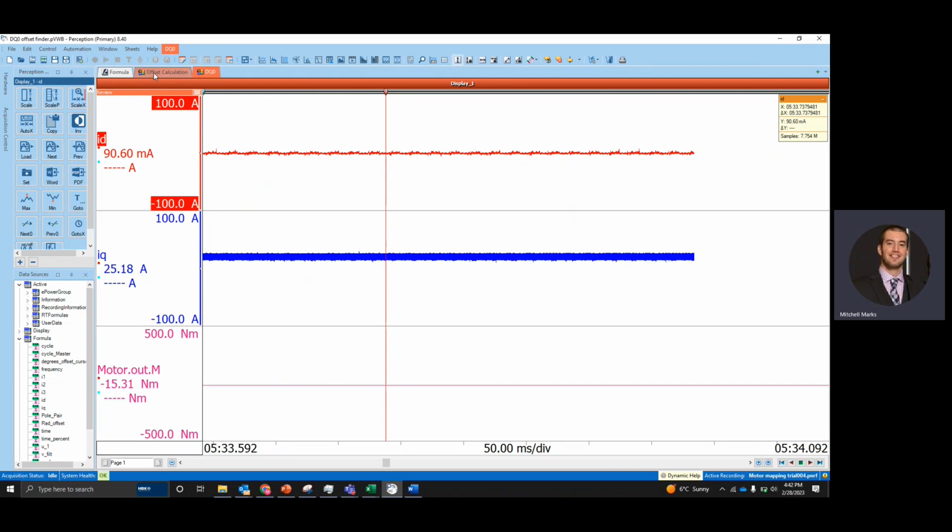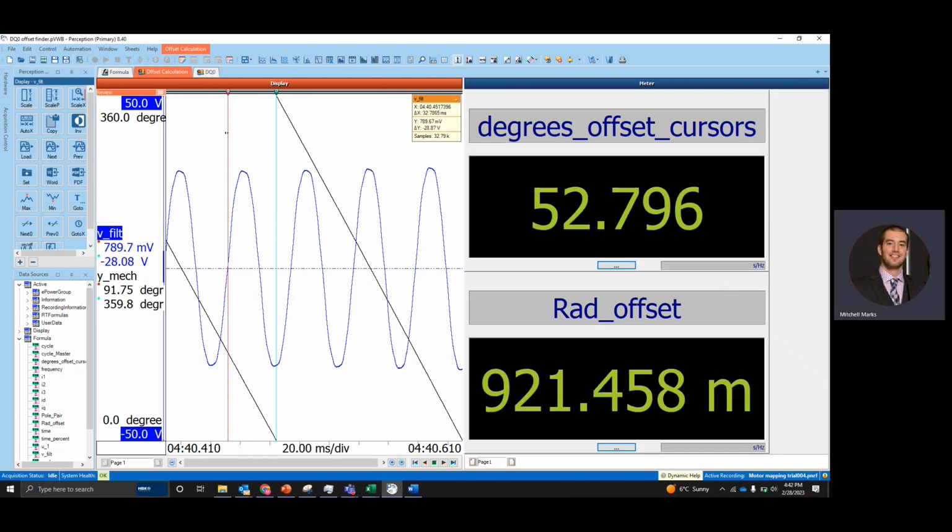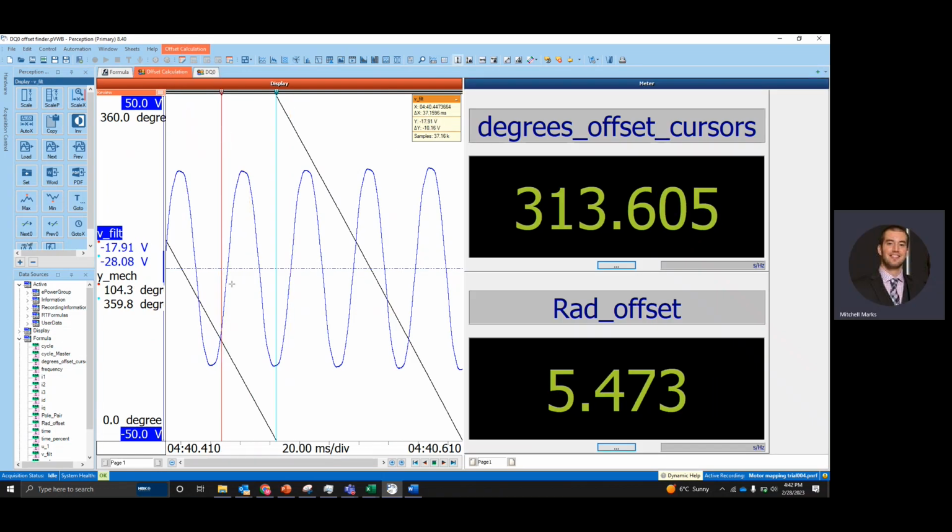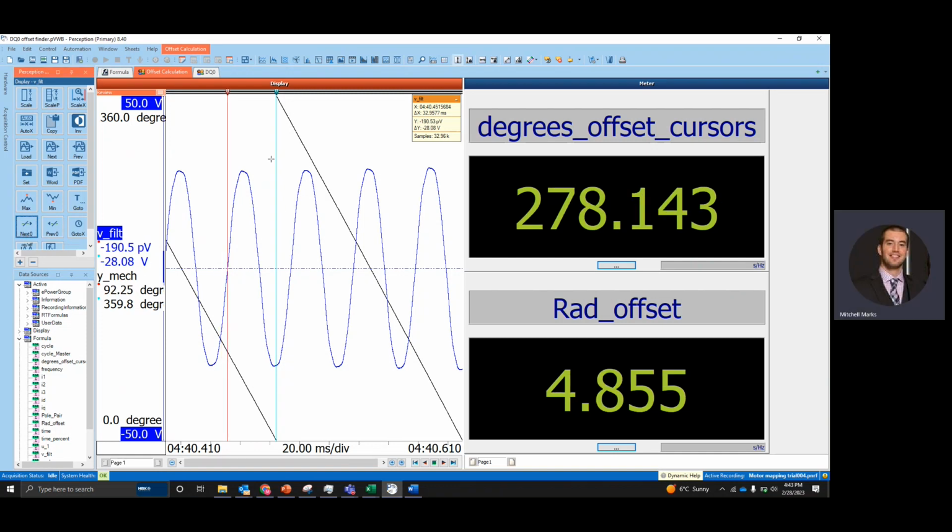So this is why we want to go to that rising edge, that negative going positive current, back EMF before the angle offset. It's because I have that absolute value in there. So I probably could code this up a little smarter. But that is an area where people go awry, and then they get that negative IQ value. So there are things you can do to change that. And this is a pretty safe way, always going to that rising edge before the angle for the calculation. That should give you the correct calculation.